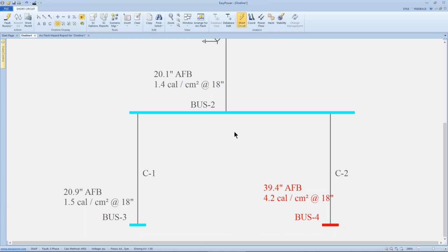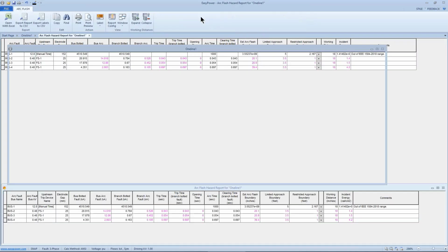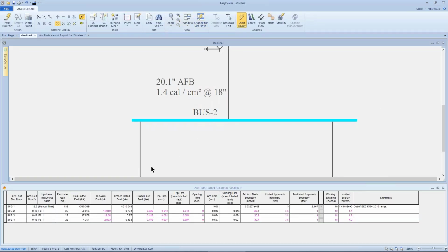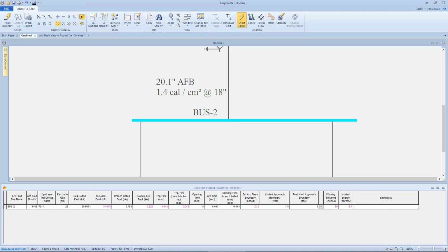Every time you do an arc flash study, you're going to reach the same spot, which is trying to understand whether or not the calculations are correct. And the tool lets me see that by using this arrange for arc icon in the top center of the focus banner. As I invoke that, the tool shows me the one-line diagram and how the calculations are being made down here on the arc flash hazard spreadsheet. It also allows me to isolate on each particular bus.